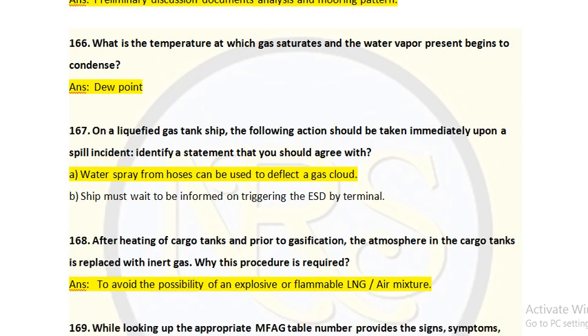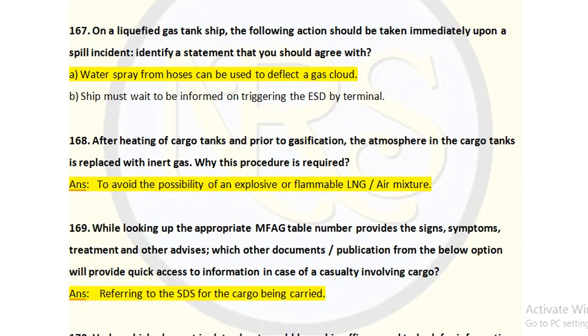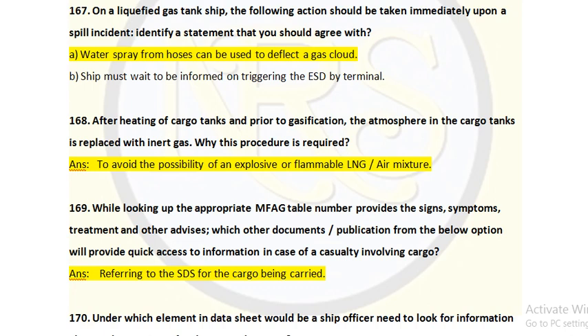Question number 168: After heating cargo tanks and prior to gasification, the atmosphere in the cargo tank is replaced with inert gas. Why is this procedure required? To avoid the possibility of an explosive or flammable LNG-air mixture. If there is air mixed directly with LNG, the LNG vapor could enter the flammable range and create a fire hazard. So inert gas is introduced to overcome this.